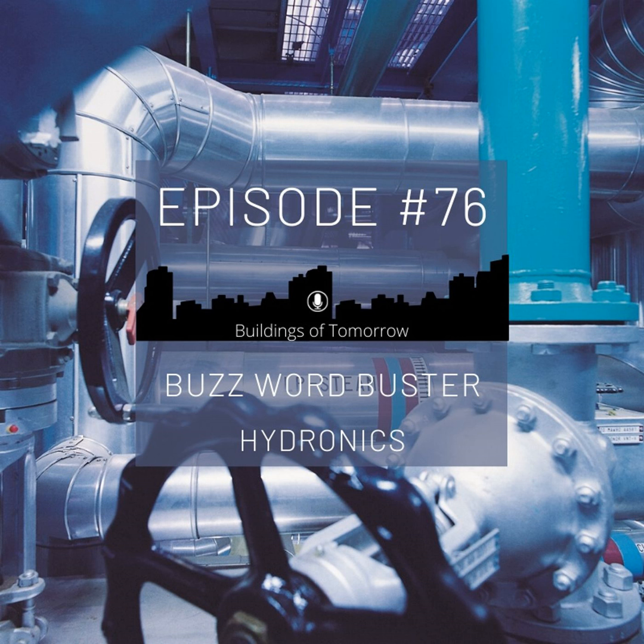So PICV stands for Pressure Independent Control Valve. And this already explains a little bit what it's all about. It's an approach for a control valve that was launched a couple of years ago and is now steadily finding its way into the hydronic circuits. And as the name says, it is a control valve, as in any other control valve. But then there is an additional differential pressure controller that basically surrounds the control valve and makes sure that pressure fluctuations in the hydronic network do not get to the control valve. So it kind of decouples the control valve from the surroundings, and by that we can achieve more stable control.